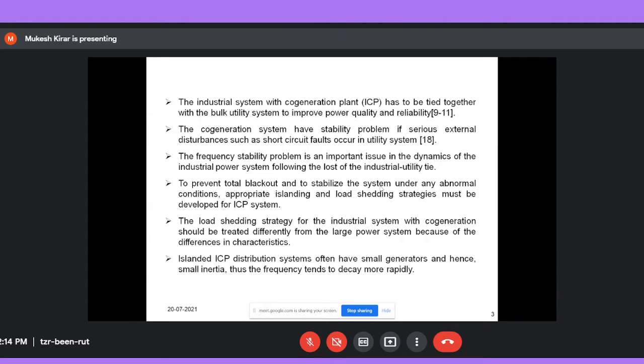If there is any abnormal operating condition in the grid, that will also affect the in-plant generator. Suppose a fault occurs in the utility grid. In that condition, the fault will also affect the industrial generation, so there is a serious issue in case of the disturbance. There will be an issue of stability. We will see the classification of stability in a further slide. There will be a frequency stability problem with the generator which is connected to the utility grid.